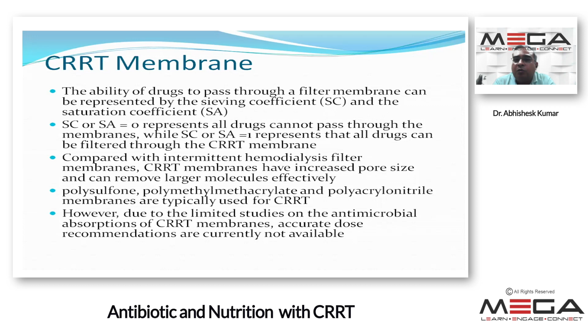Apart from that, the dilution method we use in our pump, pre-dilution or post-dilution, also changes the kinetics of antibiotics, because pre-dilution reduces membrane exposure of antibiotics, so the removal is less. If we do post-dilution, the removal of antibiotic is more because undiluted plasma is directly exposed to the membrane, so more drug is removed. So the type of dilution is the key factor for determining the effluent flow rate, which is the sum of dialysate and ultrafiltrate rate. This is considered the most important parameter for deciding an antimicrobial dose in CRRT patients.